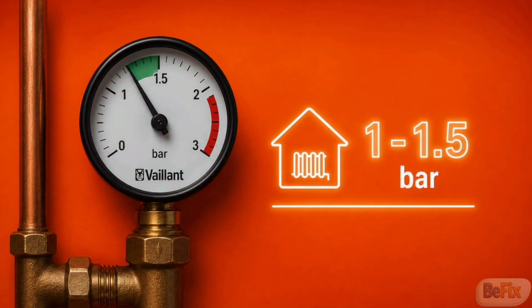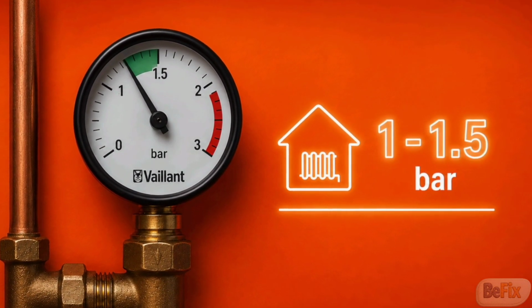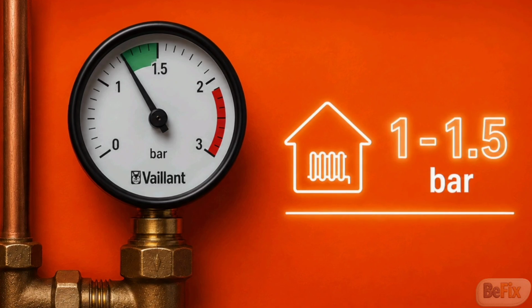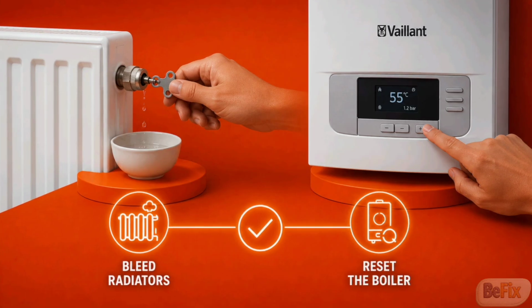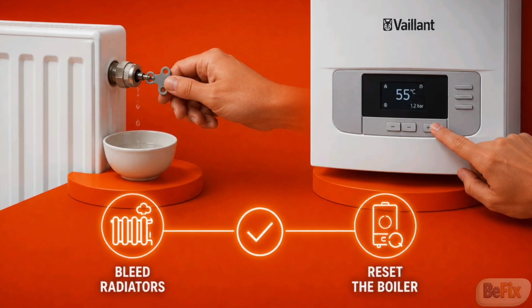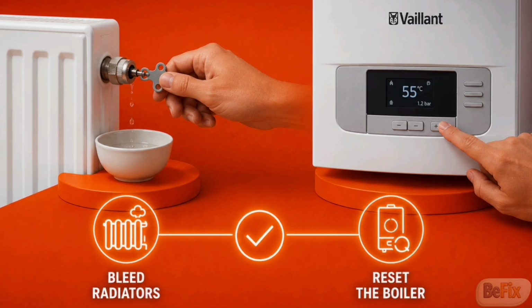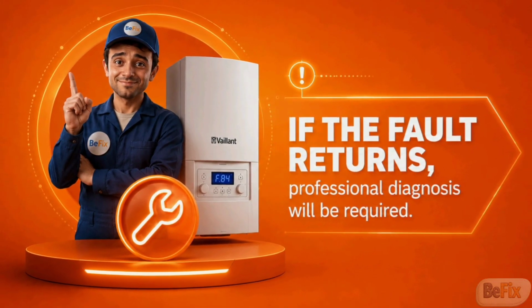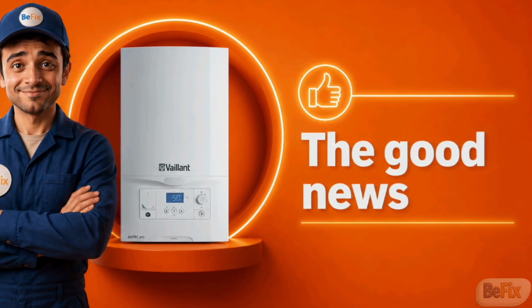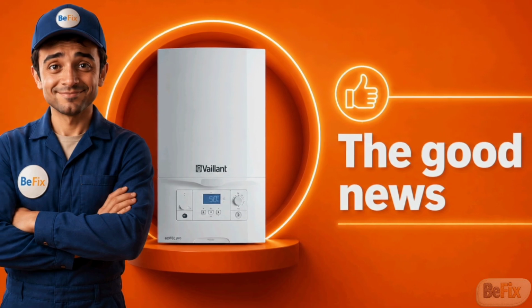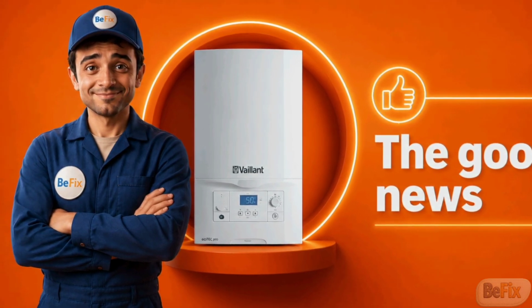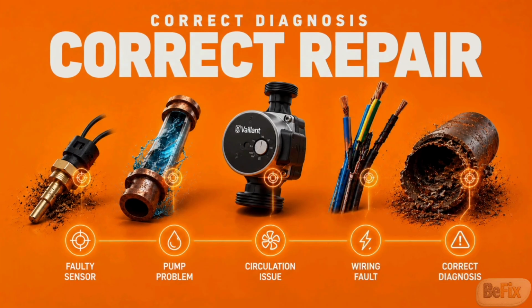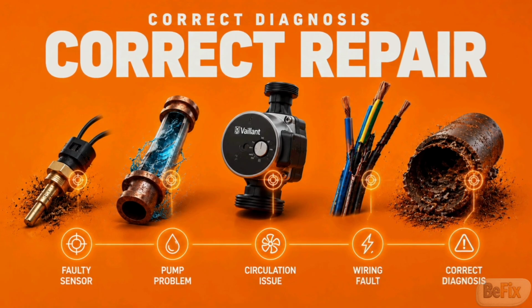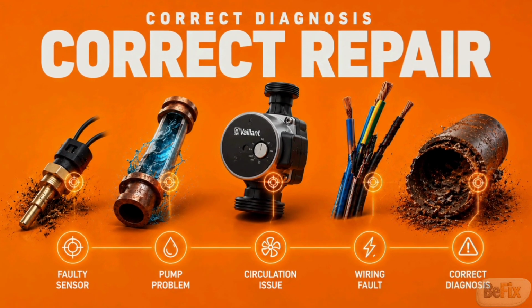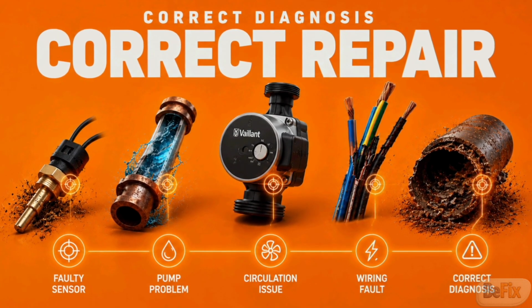Check the boiler pressure first. Most Vaillant boilers operate between 1 and 1.5 bar when cold. You can also bleed any radiators that contain air and then reset the boiler. If the fault returns, professional diagnosis will be required. The good news is that most F.84 faults are repairable once the root cause has been identified.